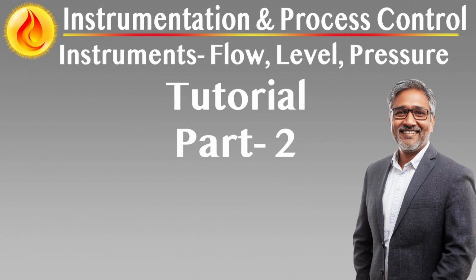In vacuum service, transmitters must be mounted at least 50 centimeters below the bottom process tapping to ensure a minimum head pressure at the sensor. This ensures functionality under static vacuum conditions, as most transmitters require 35 millibar A to operate reliably.